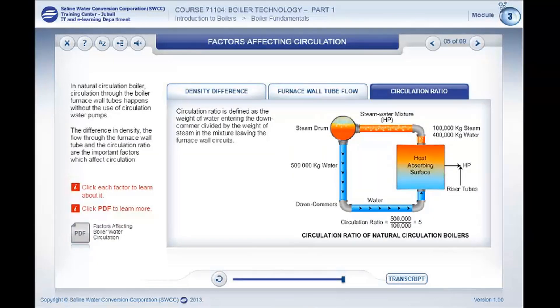Circulation ratio is defined as the weight of water entering the downcomer divided by the weight of steam in the mixture leaving the furnace wall circuits.